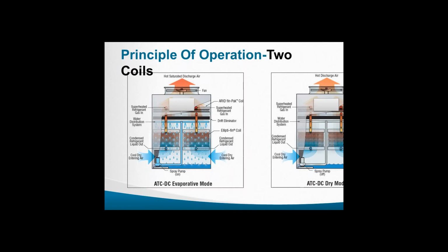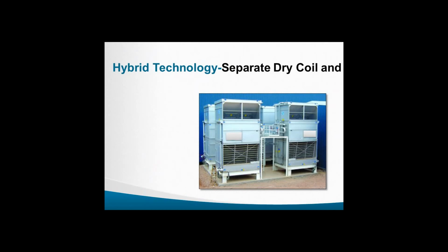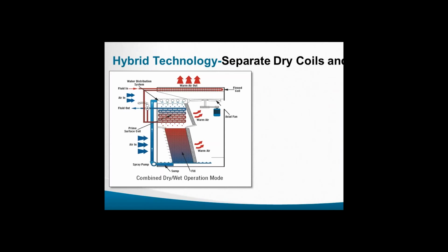Yes. So the water, the glycol, goes through the coils, and it has its own integrated pump where it's spraying the water on it. And then you have this design, which has a fill pack system in addition to a coil. In a wet-dry mode, you have the fill pack in the bottom, which cools the sump water down and sprays it over the coil. So the fluid from the system will go in the top coil there, will be pre-cooled, and then goes into the main coil, which is being cooled by the fill pack.